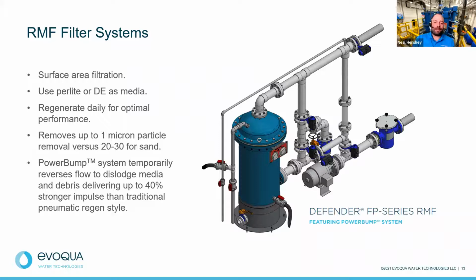This particular setup, just to give you the overview, shows, instead of a mechanical bump for the regenerative media, temporarily reversing the flow of water through the top of the tank and dislodging that media. It provides about a 40% stronger impulse to get that dirt and debris off the tubes, and then it's a very temporary, like 40 seconds or so, before it flips the valves back around and goes back into filter mode. We could probably spend 2 days just going through this type of system, but for those of you who haven't seen that piping configuration, I just wanted to point that out.